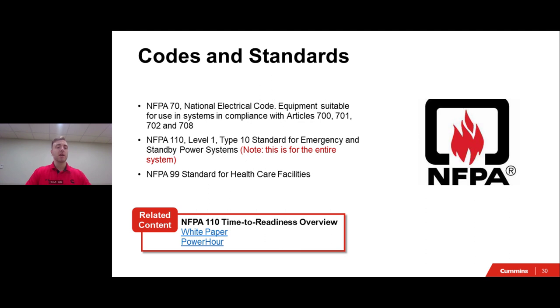Next up is NFPA 110. This is a topic that we could spend a lot of time talking about, and there have been several webinars done on this topic, but the thing to note here is that even though you might see NFPA 110 associated with the transfer switch, this code is for the whole entire power system itself. So this means that NFPA 110 is for the transfer switch and the genset and everything else that goes with it.